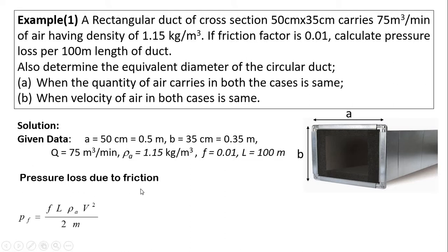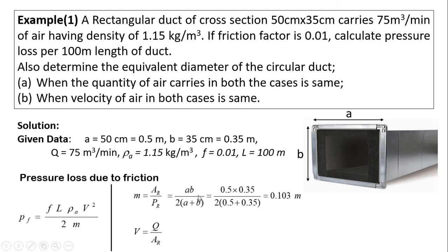First we calculate pressure loss due to friction using the formula: Pf = f·L·rho·v² divided by 2m, where m is the hydraulic mean depth. Hydraulic mean depth m = cross-sectional area divided by wetted perimeter. Velocity v = Q divided by cross-sectional area. For the rectangular duct, cross-sectional area = a × b and wetted perimeter = 2(a + b). By putting the values, hydraulic mean depth m = 0.103 m.